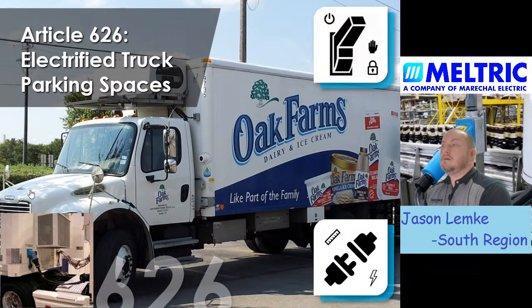So that's one thing that you need to pay attention to, is that the device has a set of things that it's able to do that the manufacturer will tell you that these devices are able to do. And you need to make sure that you're following the manufacturer's listed applications, recommendations, or how to use the product. So with our Meltric devices, we are a switch. We allow you to make the product under load and break the product under load. And we have to go through some specific tests with UL in order to be able to tell you that that is something that we allow.